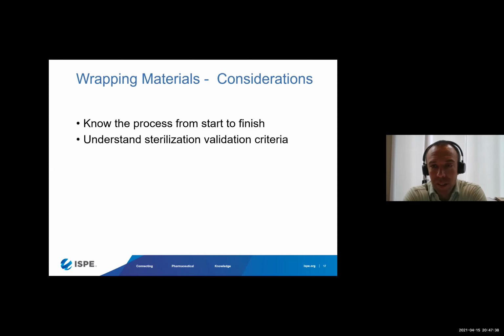Sterilization validation is not just the autoclave process, but the preparation of the parts and the aseptic presentation at the time of use. So the scope has widened, and regulators are auditing based on this wider scope of sterilization validation. So be aware of this. It's not just the autoclaving itself, but preparation through the time of use.